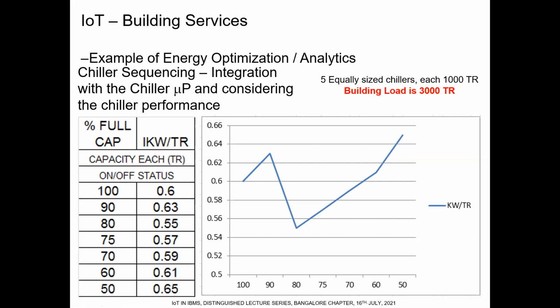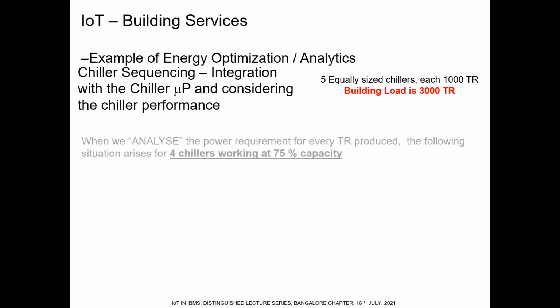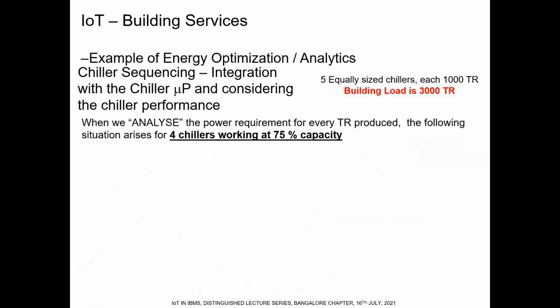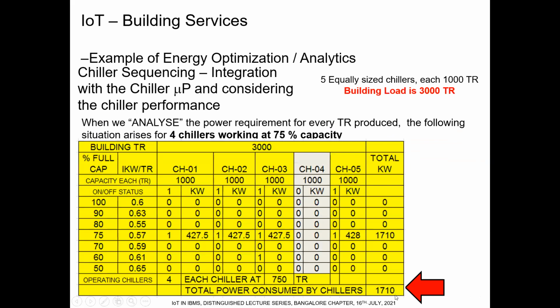So now the BMS manufacturer and the chiller manufacturer have interacted a little bit. They have gone to a next level of automation, and they say that no, it is not advisable for you to work with 3 chillers at 100% capacity. If you operate 4 chillers at 75% capacity, you will be consuming only 1710 kW. So when you are sequencing for 3000 tons, do not remove the 4th chiller. Let all the 4 chillers run at 75% capacity. This is a decision taken by an advanced level of automation.